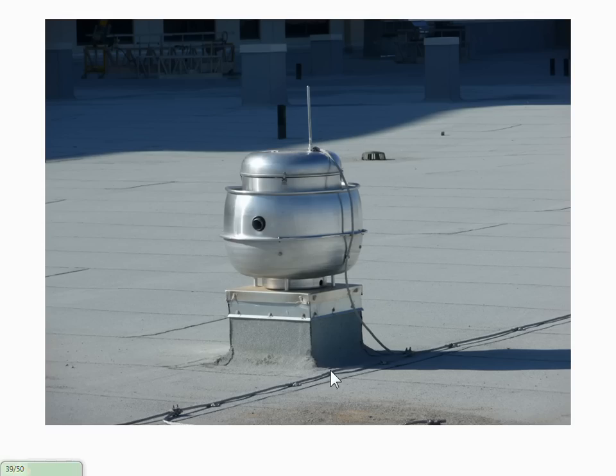Any mechanical equipment that you have on the roof also needs to be protected. It is subject to a direct strike. Basically, this is just a standard exhaust fan detail with an air terminal on top of it, connected to, as you can see, the lightning protection system here. Most people don't even know that a building is protected with lightning protection. When you're standing on the ground looking up, you can rarely see it.